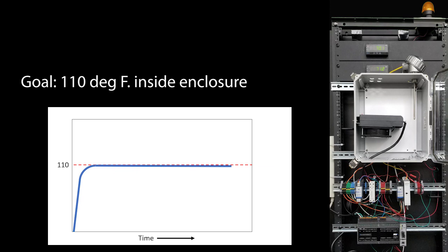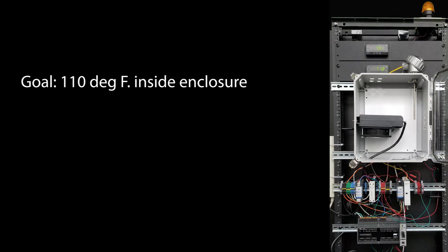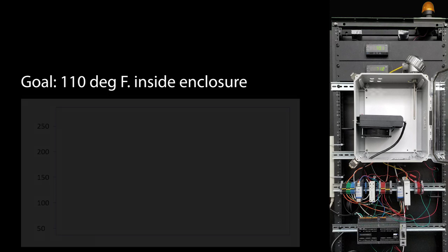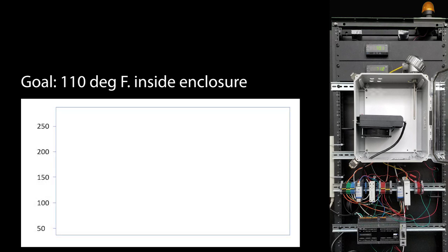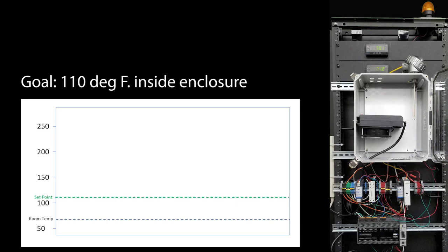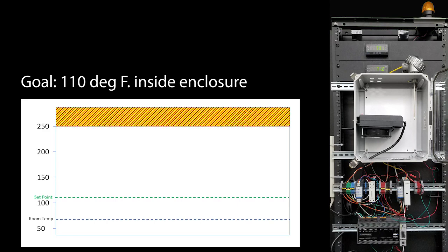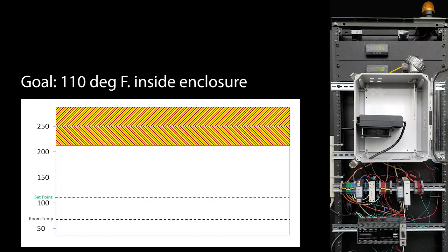So we need an exhaust fan that keeps the enclosure cool enough to prevent the cabinet meltdown but leaves enough heater power headroom so PID can get the enclosure up to 110 degrees quickly. We know the enclosure is rated for 250 degrees and I also know this heater safety trips at about 210 degrees so we need to be below that.